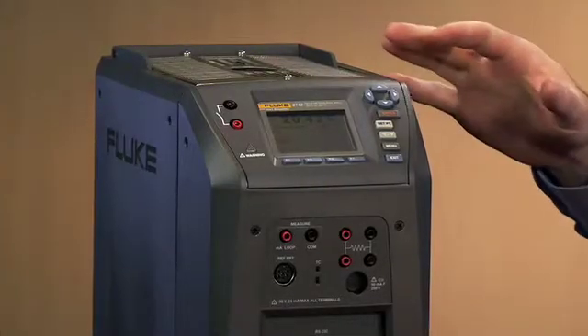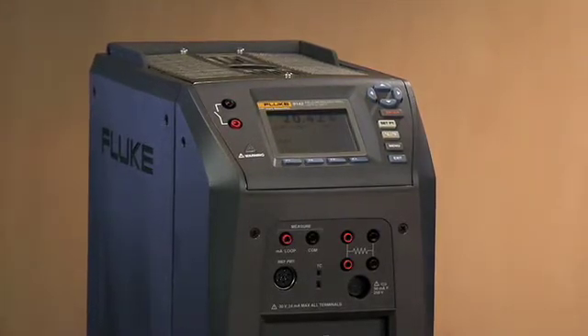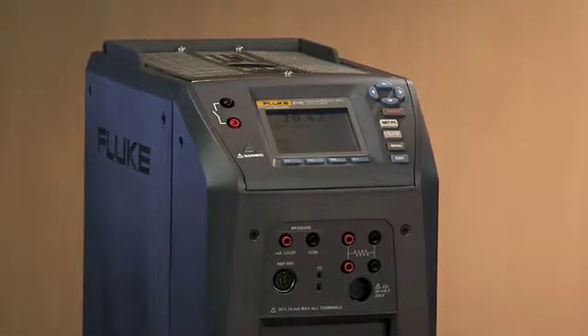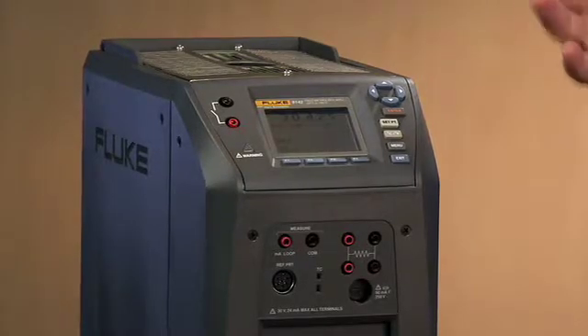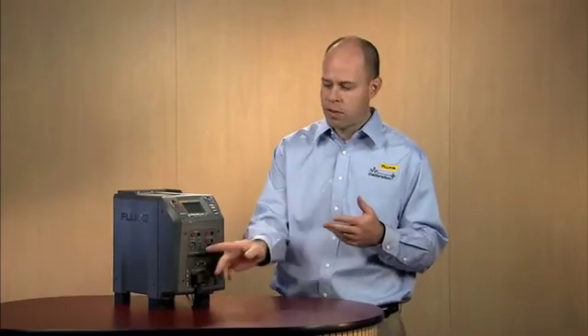With the field metrology wells, you will be ramping up to that temperature when it stabilizes. It will then soak for the defined period of time that you've given it. At the end of that period, it will then begin to record your reference PRT and also your unit under test that you have hooked up.